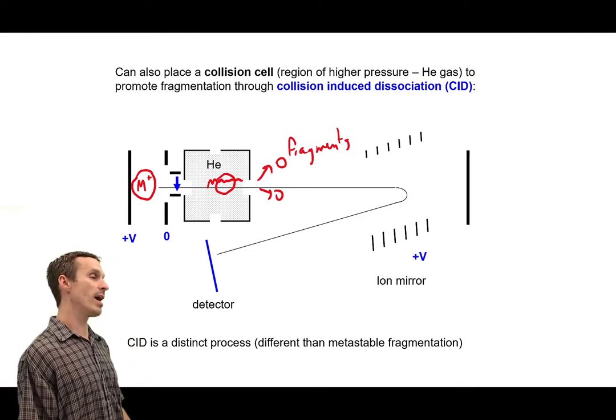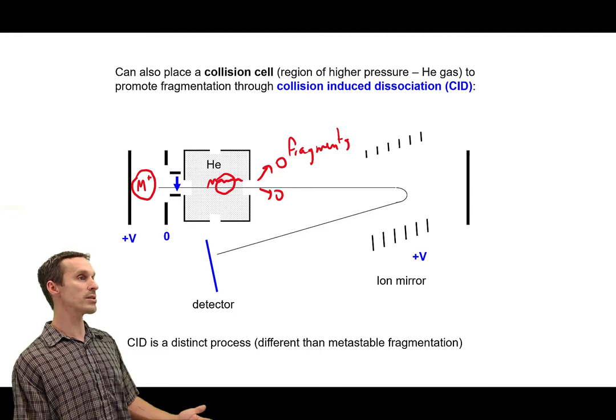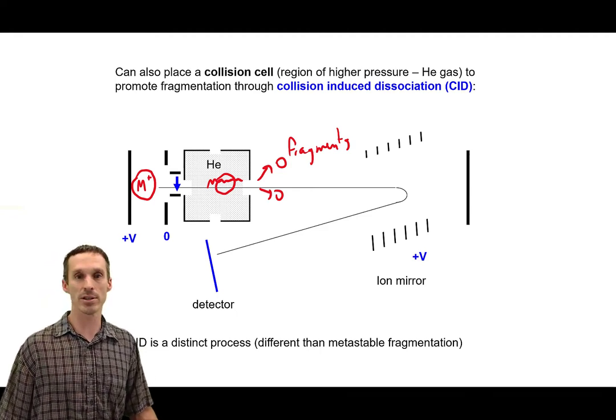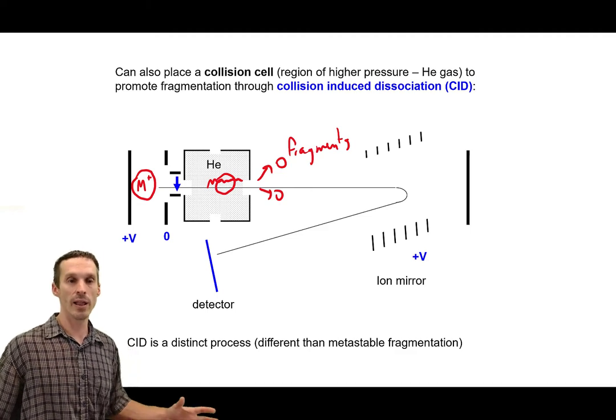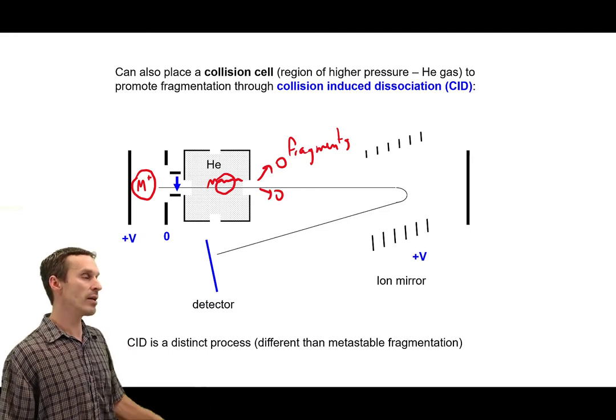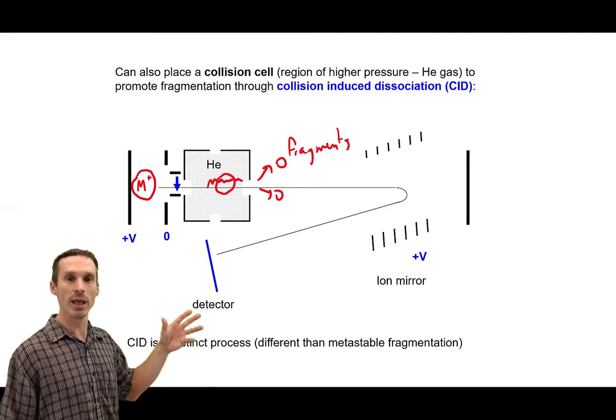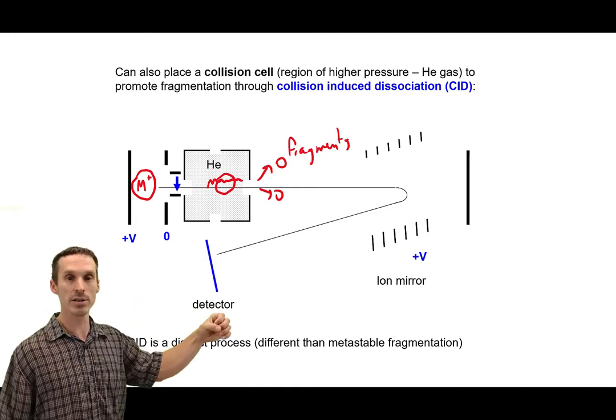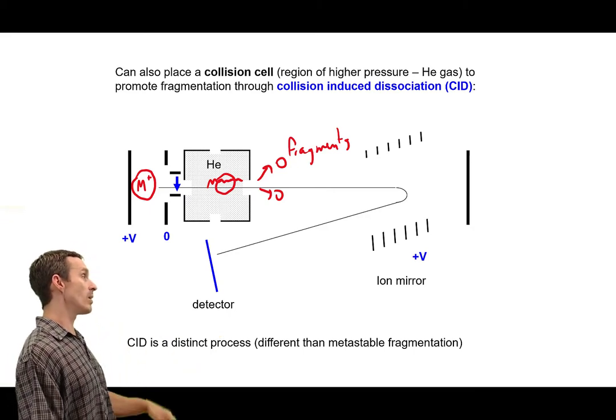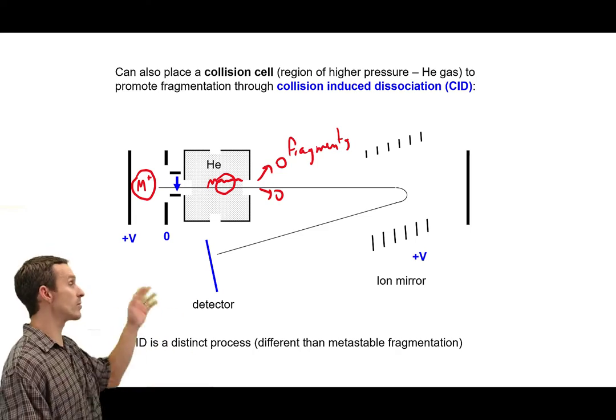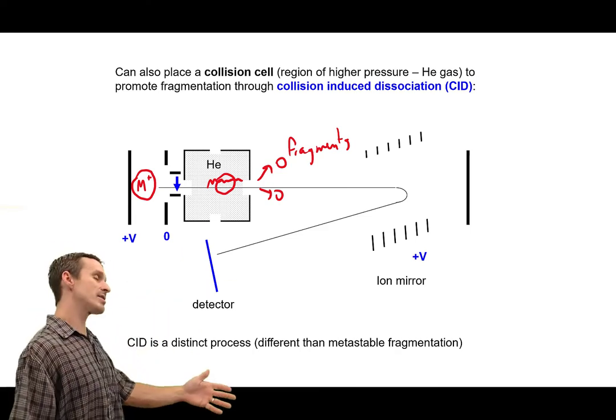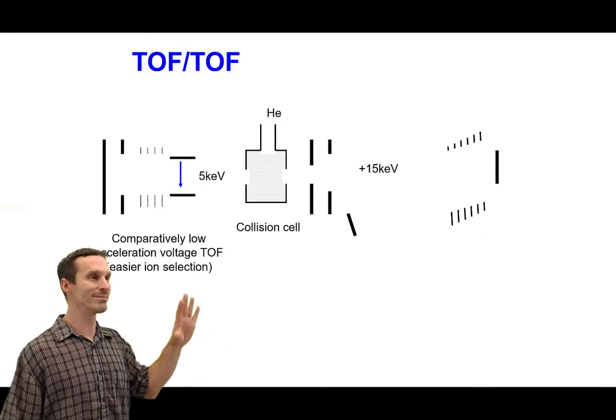Once we've selected that ion we have to break it down. So this process called collision induced dissociation is really nothing simpler than just taking that molecule and banging it into some gas. Usually we have a box within the mass analyzer that has helium gas floating in there. So there's going to be collisions, they're high energy collisions, it's enough that it breaks the molecule down. And once that happens all the pieces have new masses so they're going to fly through with their own rates.